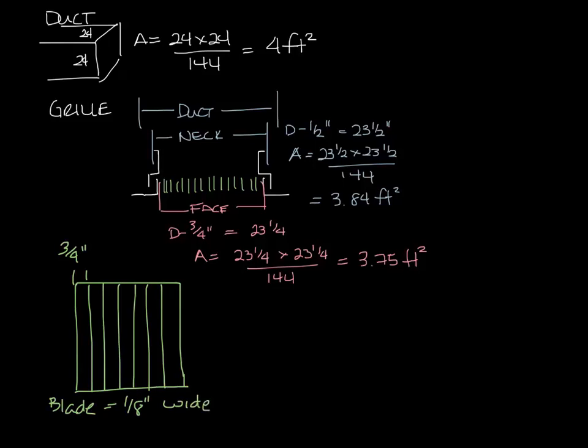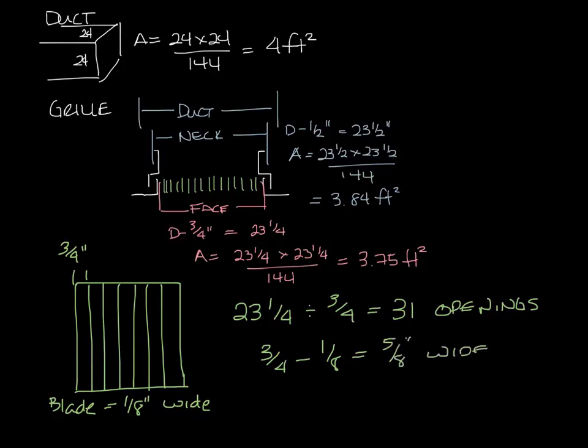So 23 and a quarter, which is our face dimension, divided by three quarters is 31. So there's 31 openings in our grill here. Each blade will take up some of that. So three quarter minus two half blades, which totals one full blade or one eighth, is five eighths inch wide, and they're 23 and a quarter inches long.